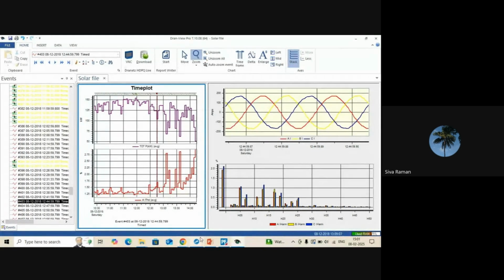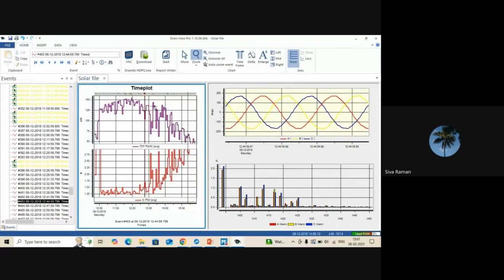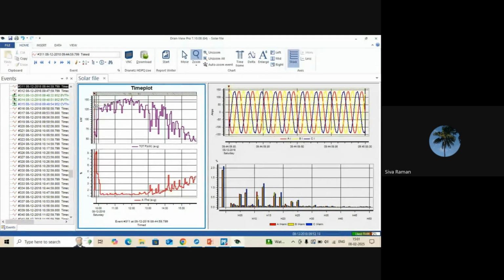When it is operating at closer to 123 kilowatt, the current THD is almost 2%, you can see. I will unzoom a little bit and go to this point, which is closer to 75 kilowatt. At 75 kilowatt, the current THD is almost 2%, but the individual order has changed.